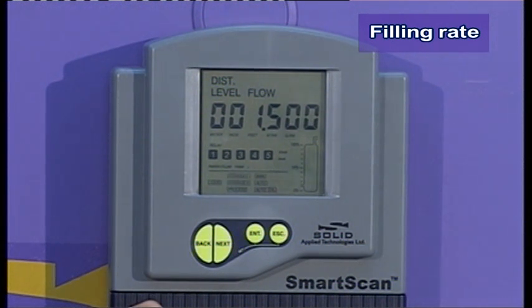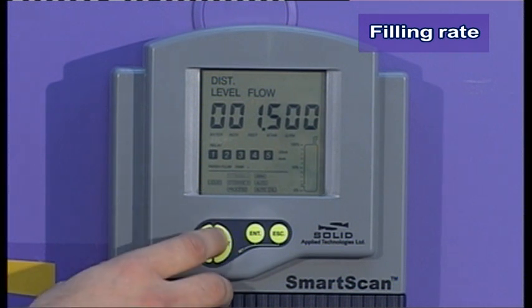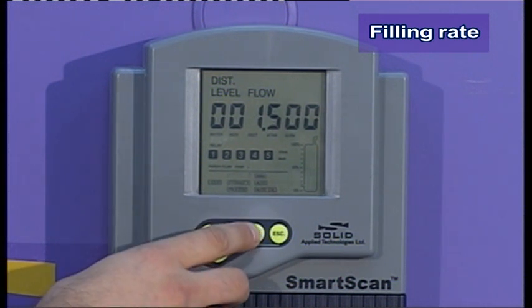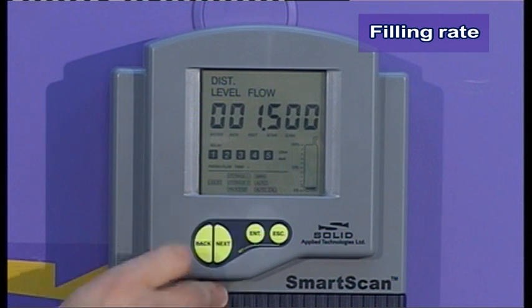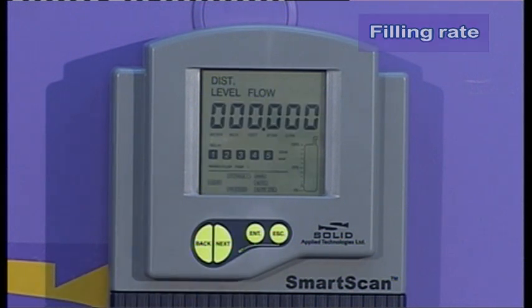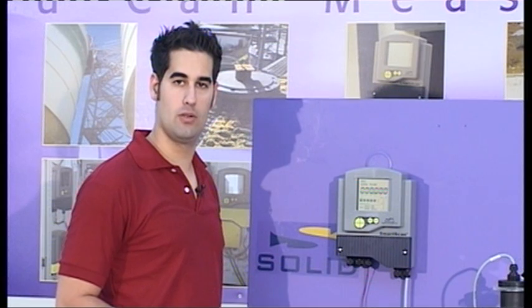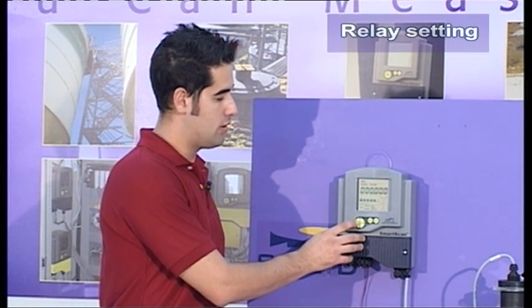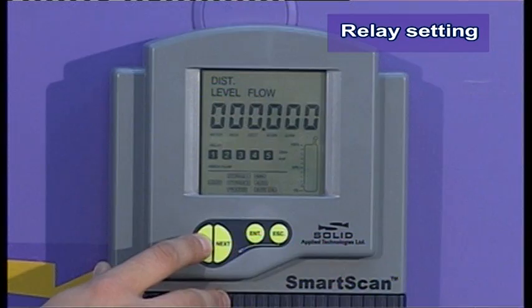Storage 2 indicates 40 centimeters per minute. And process is for process measurement. It's up to 1 meter per minute. For example, I will choose storage 1 and press enter. After we set the filling rate, we will define the relay open and close set points.